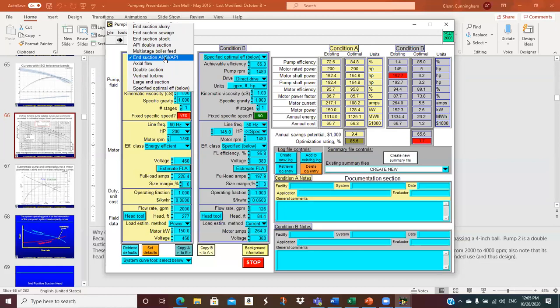And, you know, we haven't talked through all of this stuff, and we won't talk about all of these, but the different pump types include end suction, slurry, sewage, API, American Petroleum Institute, and double suction, where you're pulling fluid in on both sides of the impeller. We could have a multi-stage boiler feed water pump. And your steam systems, high pressure steam systems, typically have multi-stage pumps.